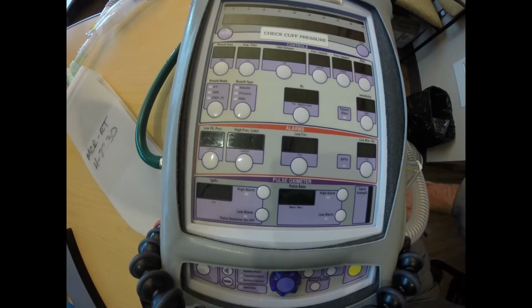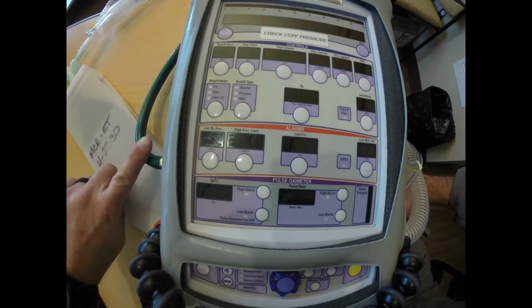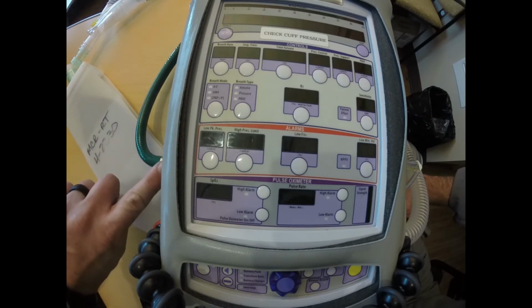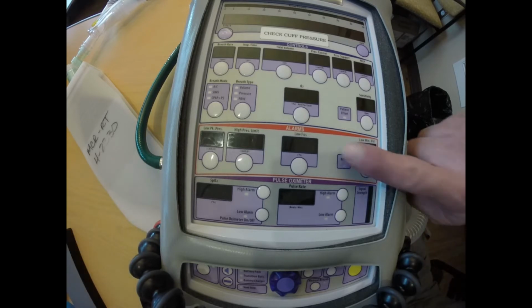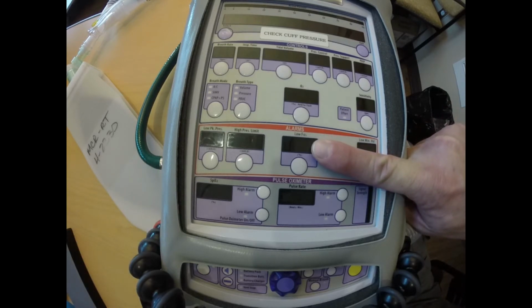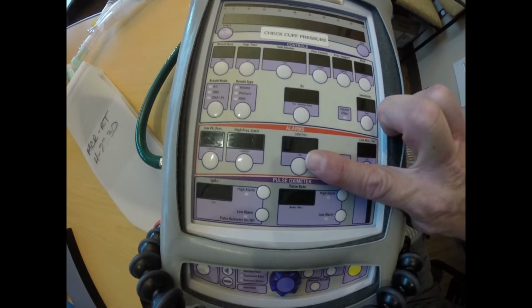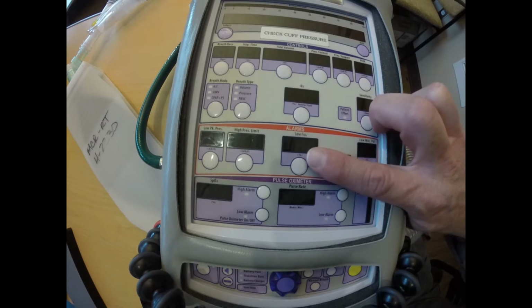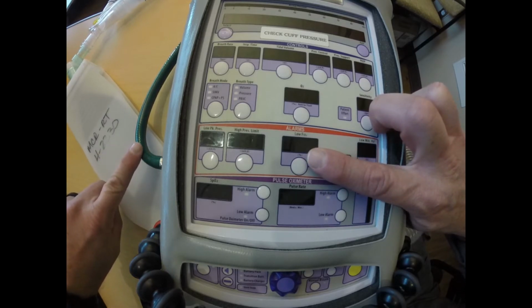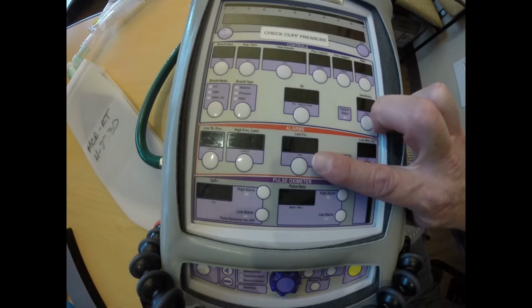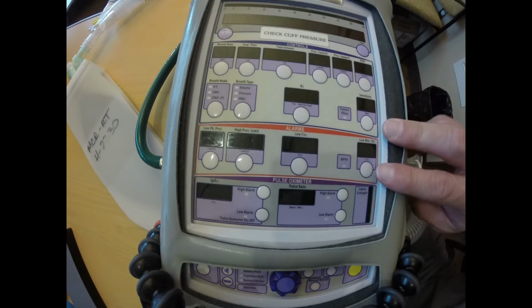A couple of things to note when using CPAP and CPAP plus pressure support is that I can provide oxygen to my patient via a high pressure hose, or I can use an oxygen supply tubing and a Christmas tree in the low pressure setting if I choose to do that. If I choose to use the low pressure setting, the ventilator will entrain atmospheric air to help me run my turbine, which may be advantageous in some people. It doesn't matter if I use the low pressure system or the high pressure system. I have to use a mask that is non-vented for this ventilator to be effective. So let's go ahead and place a patient on CPAP.